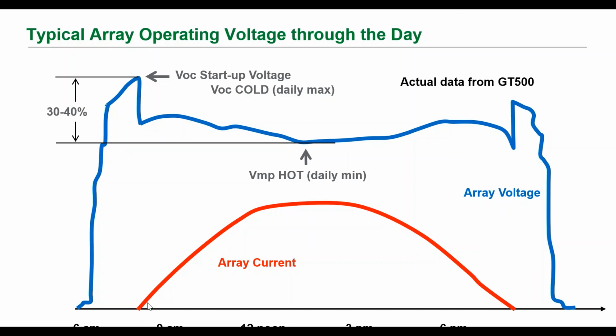So here you see current starts to flow. So this is the current, this is voltage. In the morning at 6 a.m., no current because irradiation is very less. High voltage, you see. This voltage will be some 900 volts in a 1000-volt system. By 7:30 or 8 o'clock, current starts to flow because the sunlight will be a little brighter. So you'll see some irradiation. Current will be there. Then voltage will see a dip. Suddenly voltage will decline, and the product of these two will be the power. Then as we move on in the day, gradually current will also increase. So at noon time, current will be maximum. Then after that, the sun starts to set, and then it will decline.